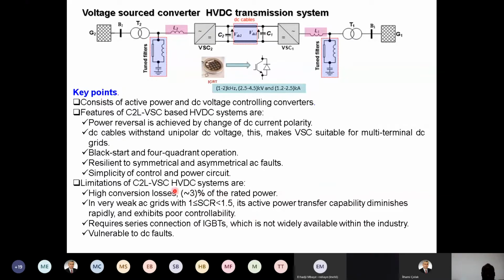But this limitation is now likely addressed in new topologies. And in very weak AC grids with SCR in the limit of 1 and 1.5, its active power transfer capability diminishes rapidly and exhibits poor controllability. But this is also not limited to conventional VSC. This is true of all VSC. And one of the problems in HVDC, because now the highest IGBT rating is 6.5 kV, if you need to operate this one at 300 kilovolts, you have to put a large number of devices in series. But this technology exists, but it's not widely available within the industry. And also it is vulnerable to DC faults, because during a DC fault, this capacitor also discharges current, then the fault current becomes significantly higher to handle.